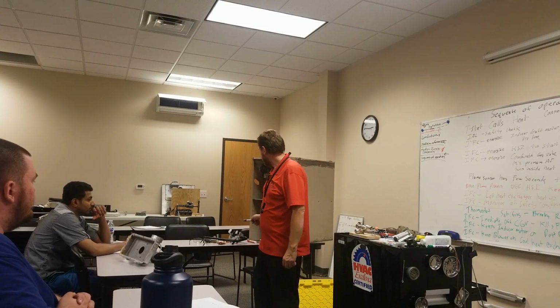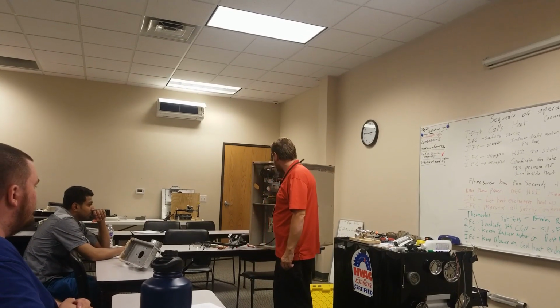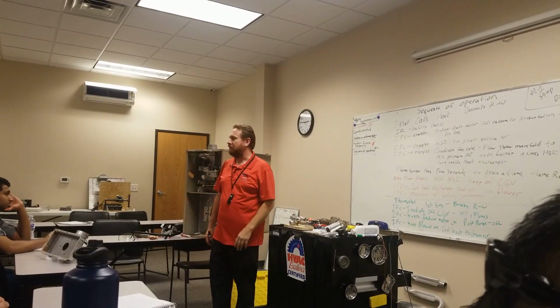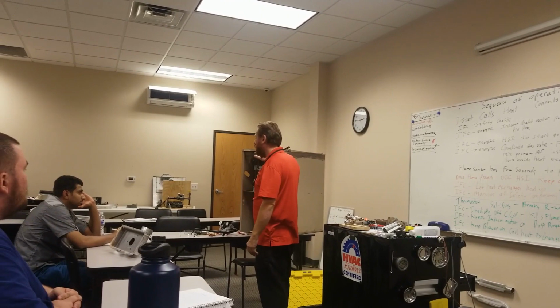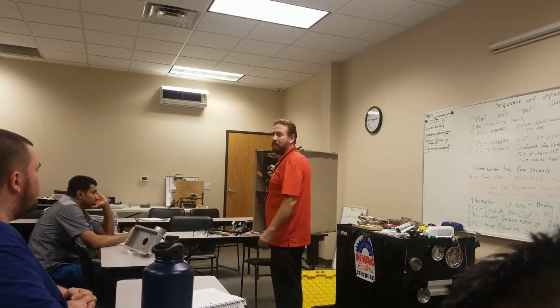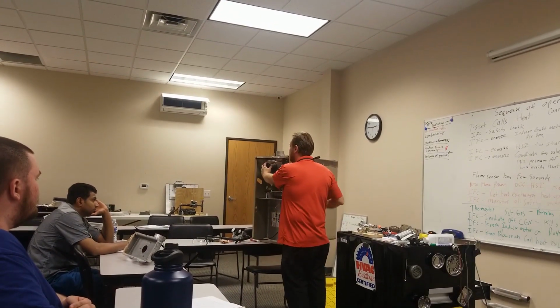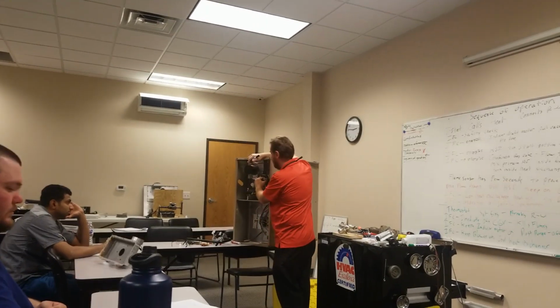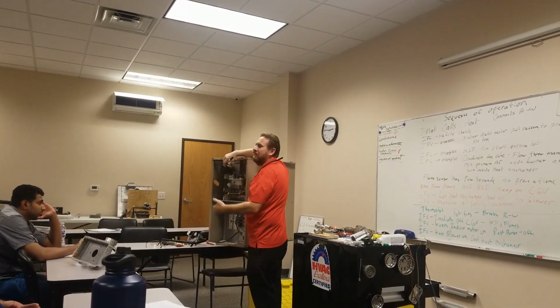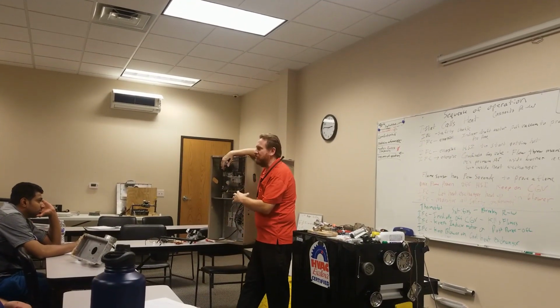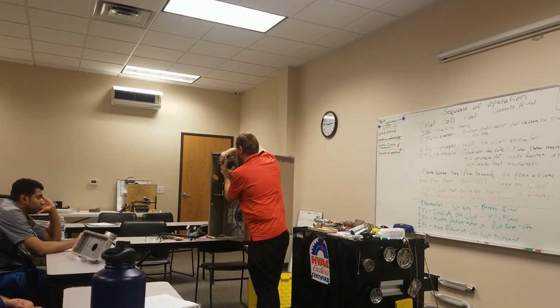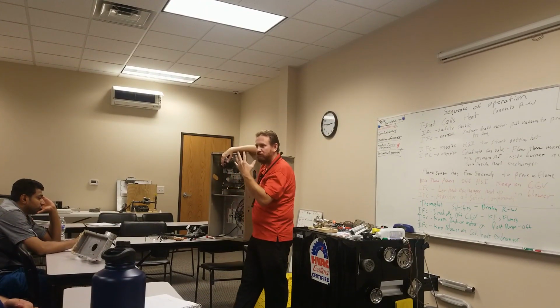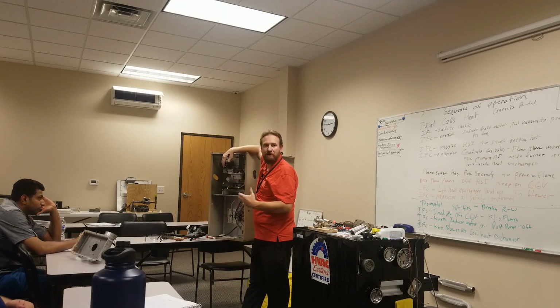I want you to use the wiring diagram and follow the wires. Identify all these components we just talked about. Go through the sequence of operation. Even if it's not running, go through and touch every component as you say it: inducer fan motor, inducer draft motor, combination gas valve, high limit switch. I want you going through it and touching it. I want you to connect what these components are to the unit so that you know them, so when I ask you about it, you know what I'm talking about.